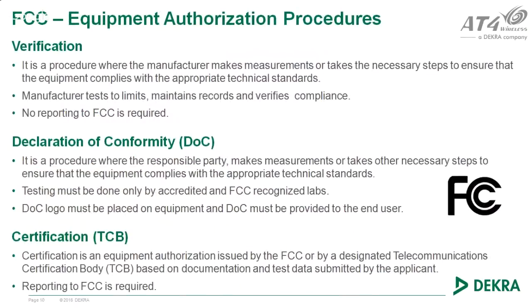With regard to the approval routes in FCC, there are three different. The first one is verification, and it applies for devices which do not have any radio interface. It is for EMC approval. And the second one, the declaration of conformity, is similar to verification. It applies to similar devices. There are some differences if it is a computer device, if it is a peripheral device, but essentially both procedures are quite similar, and both are for devices without radio. And the third one is the certification procedure. It's what we call TCB.